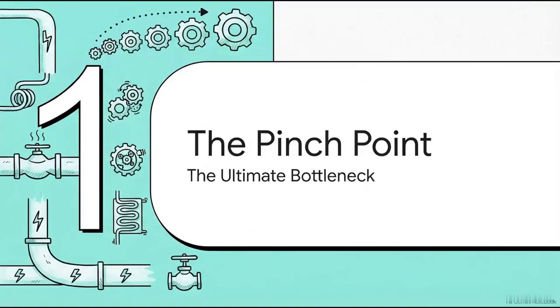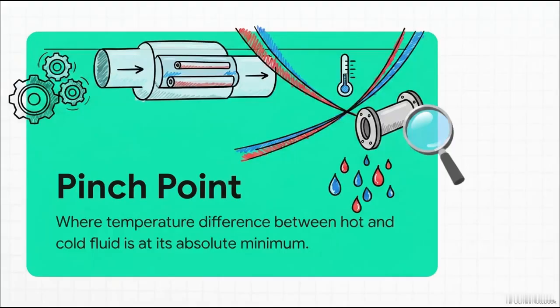Part one: understanding the pinch point, the ultimate bottleneck. So what exactly is a pinch point? Conceptually, it's pretty simple. In any heat exchanger, you have a hot fluid transferring its energy to a cold fluid. The pinch point is the precise spot in that process where the temperature difference between them is at its absolute minimum — basically, they are as close in temperature as they will ever get.